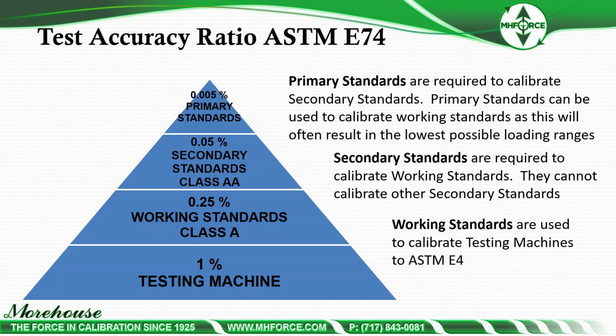So basically what I'm saying here is ASTM requirements, it's using TAR, test accuracy ratios, 50 parts per million, or 0.005%, 0.05%, 0.25, and then 1%. So at the end of this, it's a closed system working with TARs to ensure that the TAR is 4 times better than the testing machine, and then that the secondary standards are 5 times better than the working, and that the primary standards are 10 times better than the secondary.